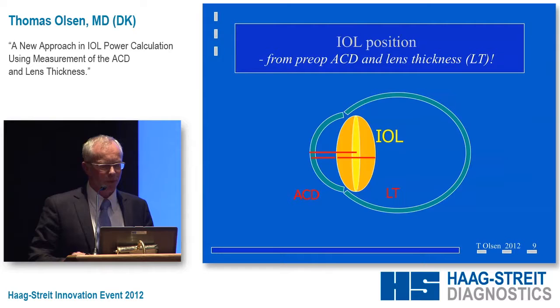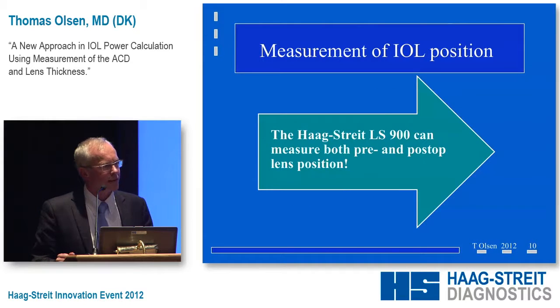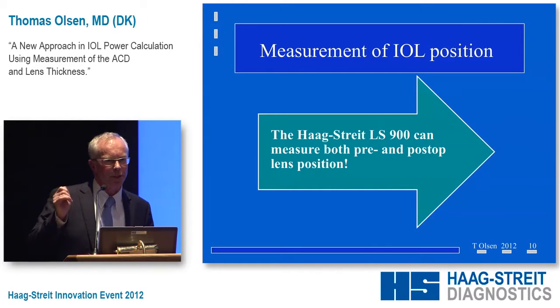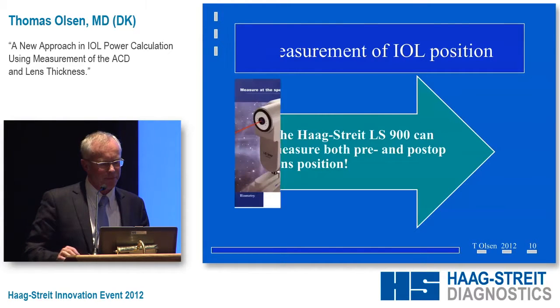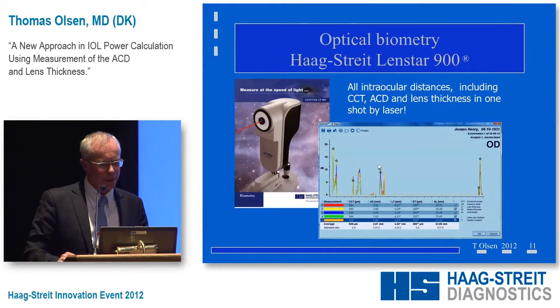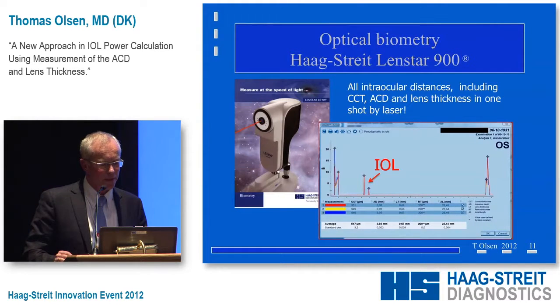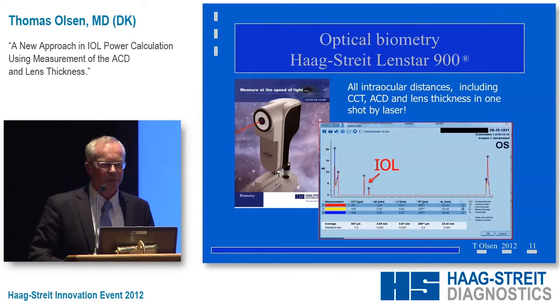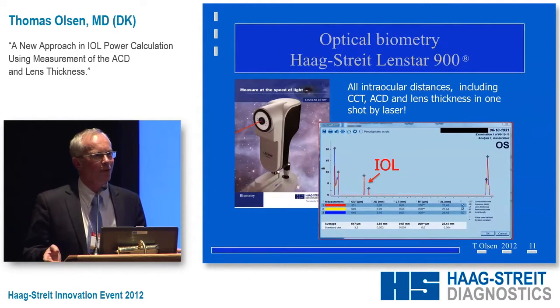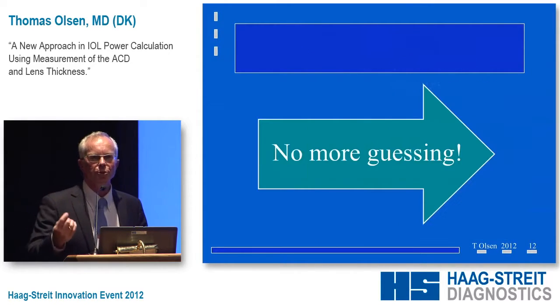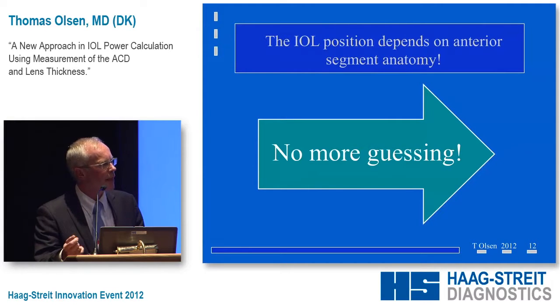If we measure the anterior segment structure — that is the anterior chamber depth and the lens thickness — we can come up with a very nice correlation of the final position of the implant in that eye. With the Haag-Streit LenStar machine, you can actually measure the IOL position with laser biometry, so it's very accurate. This is first shown for the phakic eye, and lens thickness can be measured with high accuracy. The final position of the implant comes up very nicely, and you can also measure the thickness of the IOL and from that derive the IOL power.